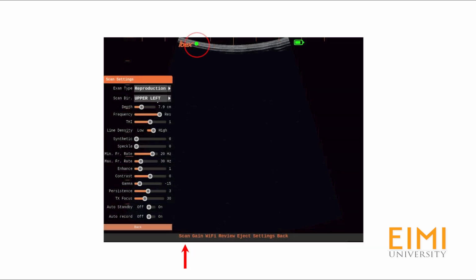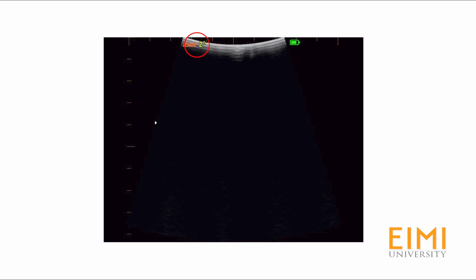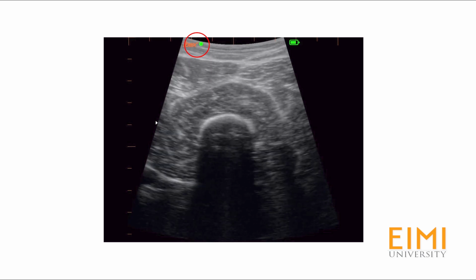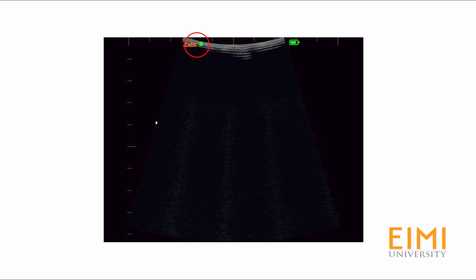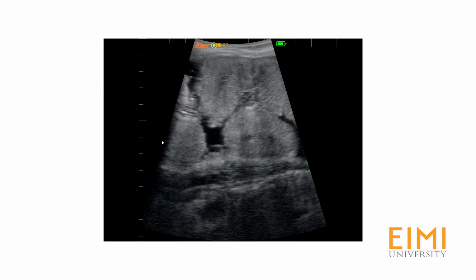Auto standby mode can be enabled in the scan menu. This feature pauses the live image between patients. Once the transducer array detects contact with tissue again, the live image resumes. This feature reduces battery consumption by approximately 20%. To take a linear measurement on screen, press the select key while in freeze mode. Use the directional arrows and select key to choose start and end locations for the measurement. When the graphics are blue, they can be moved. Once the select key has been pressed, they're committed to the location and turn orange.